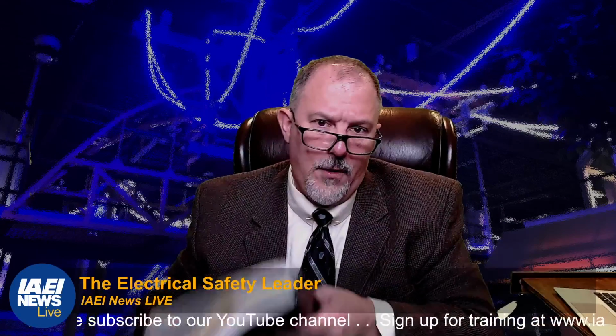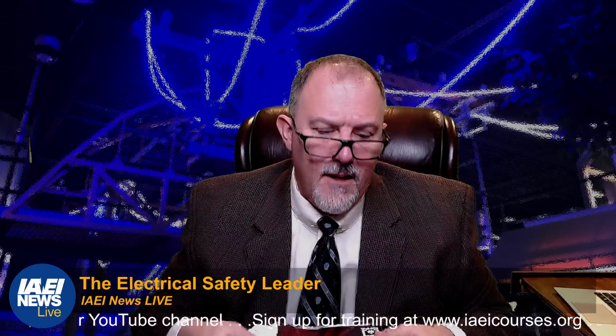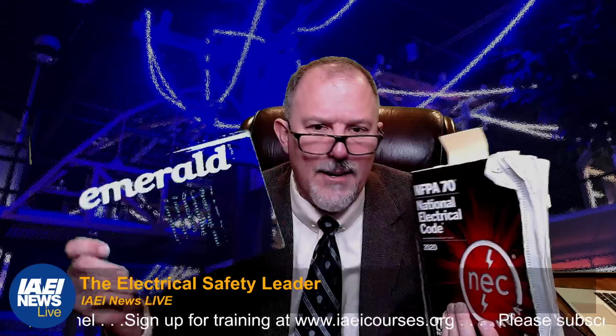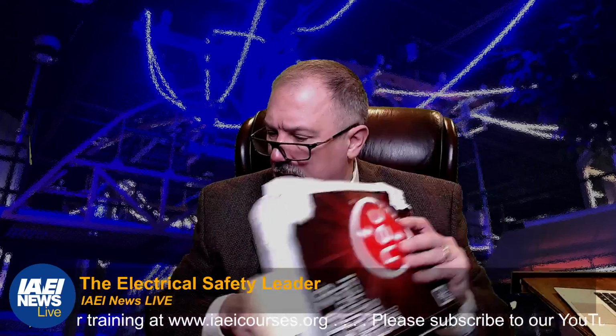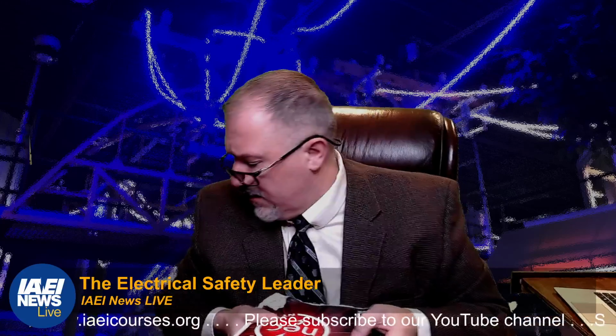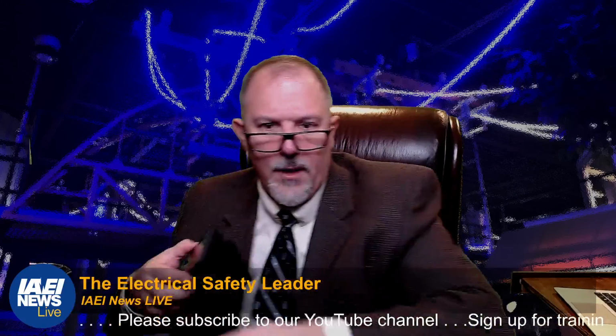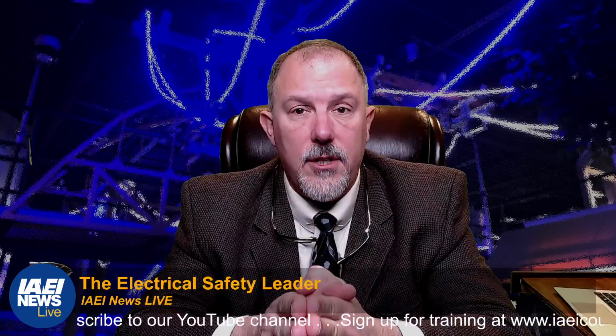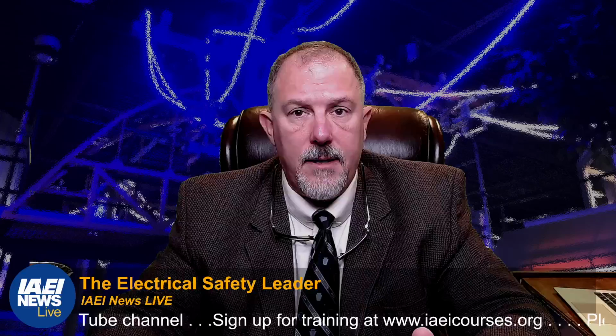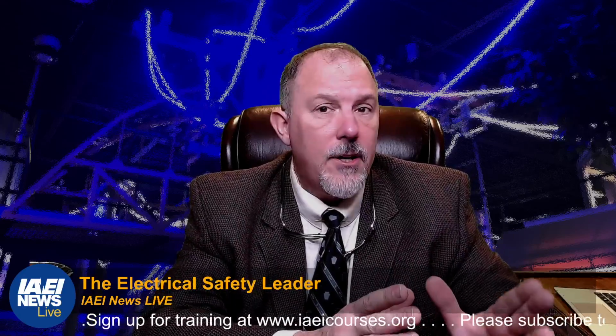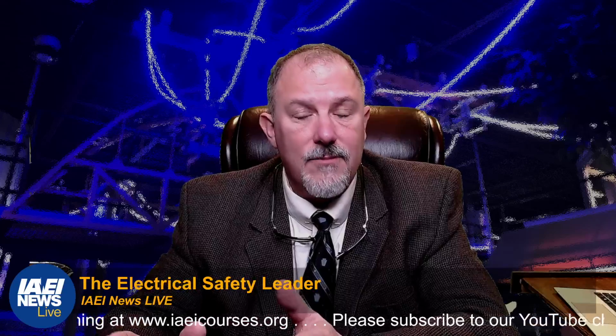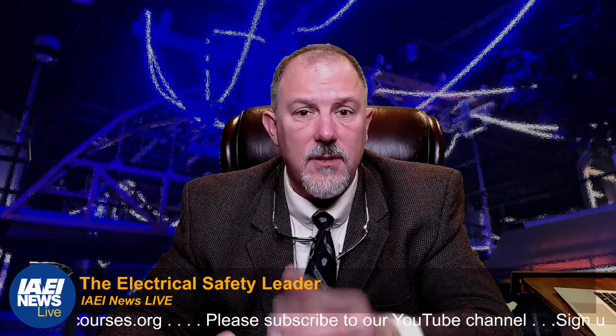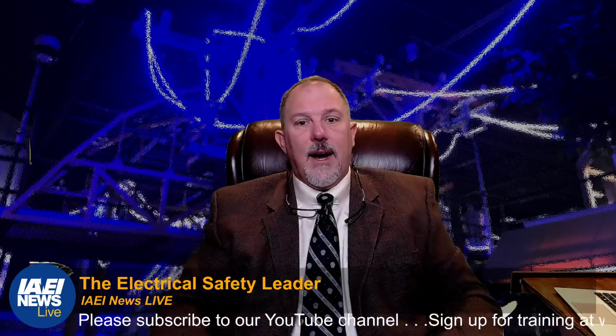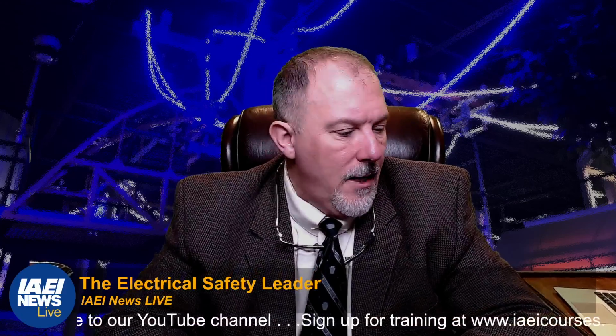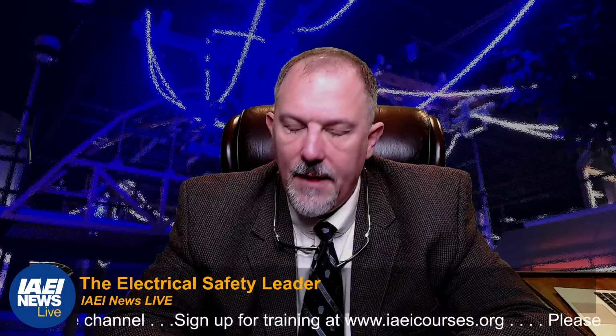All right, so that's sort of an introduction and overview of the requirements that can be found in the National Electrical Code. You got a reference here in the Emerald Book. It's IEEE Standard 1100. And I'm sure you have other reference materials out there that you may know of that are of interest for you. But remember, surge is a solution that will protect equipment over a period of time. Surges are overvoltage, but not all overvoltages are surges. We've got swells, we've got other types of considerations. And I think we did some damage on surge. All right, so that's all I had to say about surge.